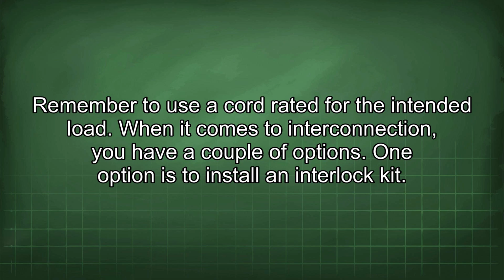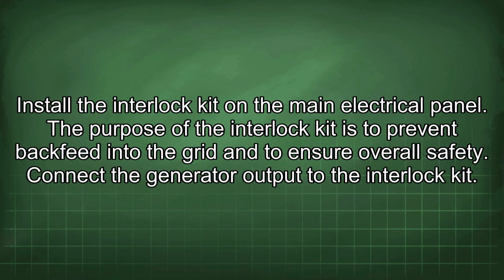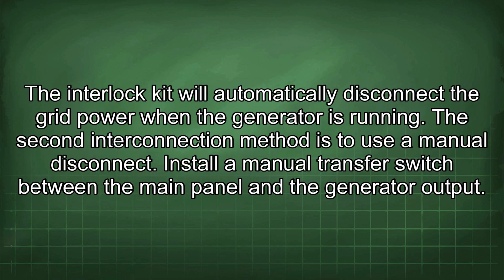When it comes to interconnection, you have a couple of options. One option is to install an interlock kit. Install the interlock kit on the main electrical panel. The purpose of the interlock kit is to prevent backfeed into the grid and to ensure overall safety. Connect the generator output to the interlock kit. The interlock kit will automatically disconnect the grid power when the generator is running.